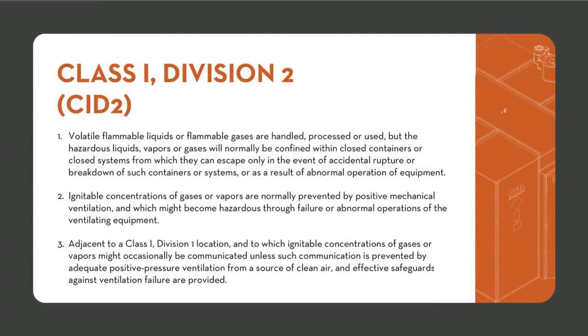Moving along to C1D2. It's a lower rating than C1D1, but it still is rated electrical, and it's not just your average kitchen electrical. Generally, what you're going to see required in C1D2 rooms would be something like ethanol or isopropyl alcohol. For cannabis extraction, we generally see ethanol. Ethanol is a liquid at room temperature. So if you're opening a vessel, you're not going to have a quick leak of liquid. You would have a quick leak of gas. So you would have to have something more drastic happen to your system to spill a bunch of ethanol.